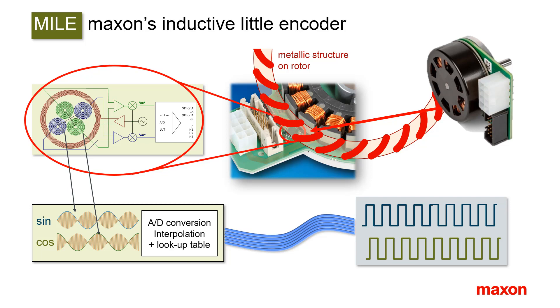For the MILE and flat motors, there is no index channel possible. The resolution of the MILE lies in the range of 256 to 6400 counts per turn; the larger the motor diameter, the higher the maximum number of counts. The large diameter of flat motors combined with the lookup table correction results in rather high accuracy. The MILE encoder on flat motors can be used for high and low speed control within the specified operating range, and positioning can be done with quite high accuracy.